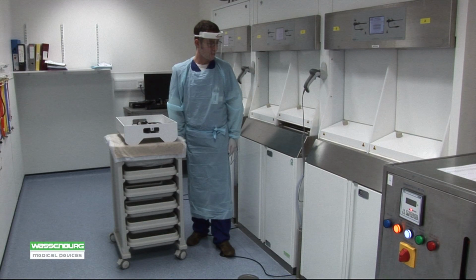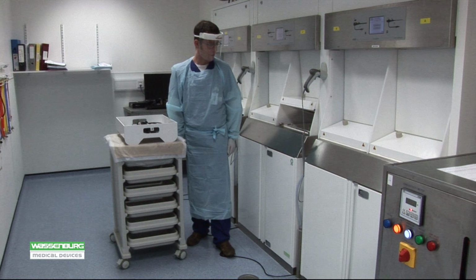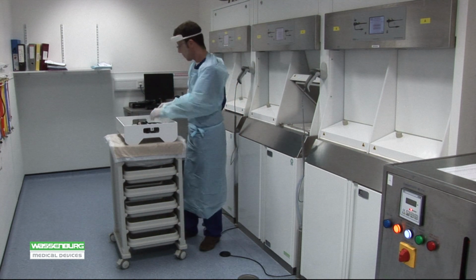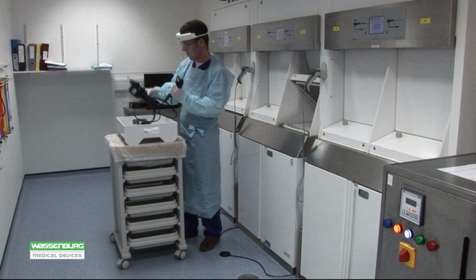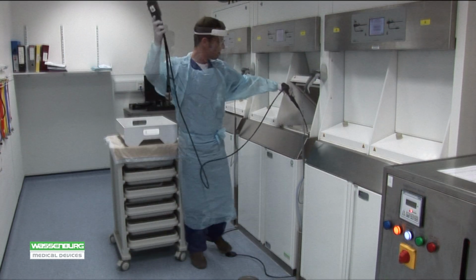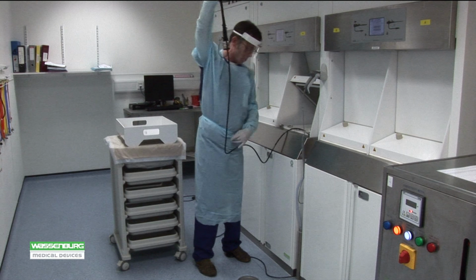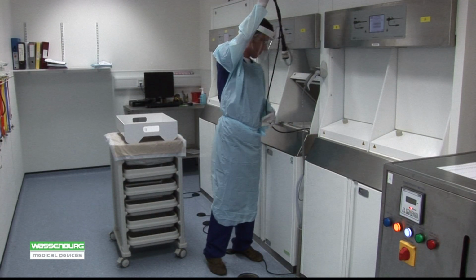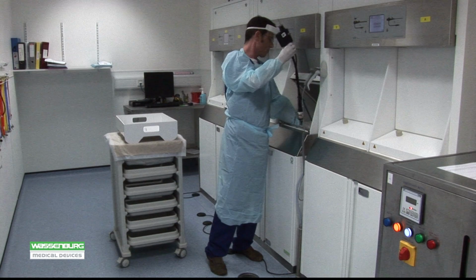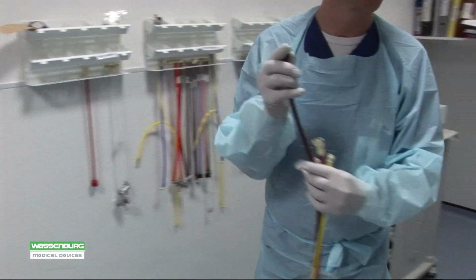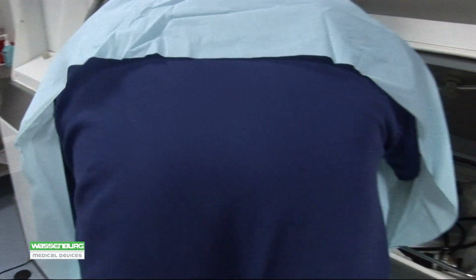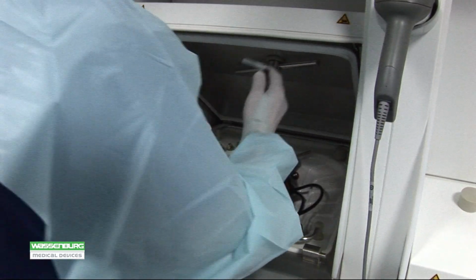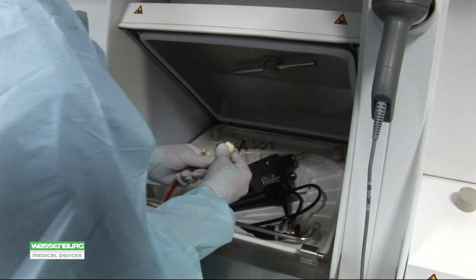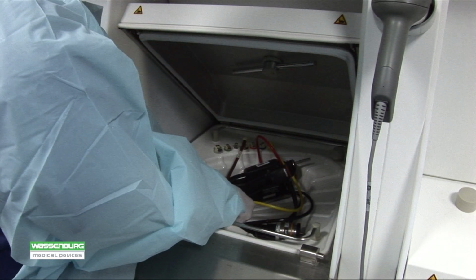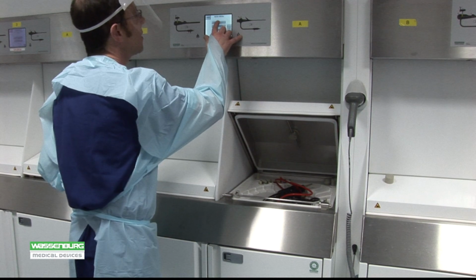Lid opening operation is quick and silent and hands-free using the foot pedal. The chambers operate independently. Manually cleaned scopes are loaded into an available chamber. All channels are connected to the individual circulating pumps using the specifically designed connectors and color-coded tubing. The channel separator is fitted into the valve housing. Each WD-440 has 2 chambers that operate independently, allowing scopes to be loaded or unloaded, whilst the other chamber has a cycle in progress.